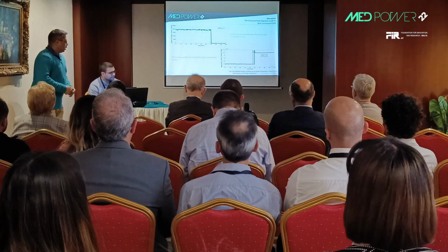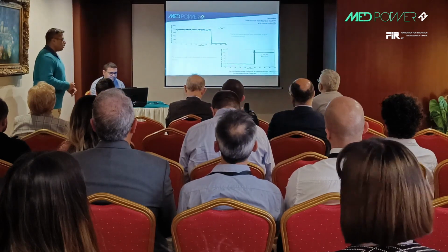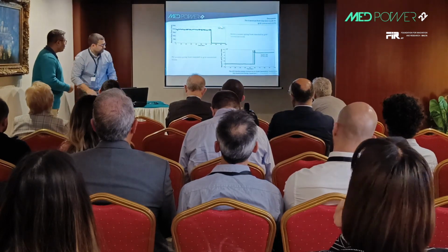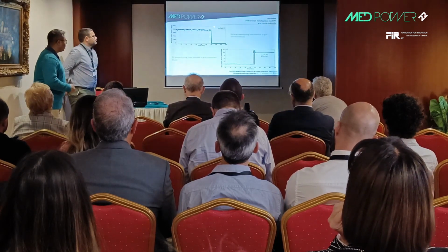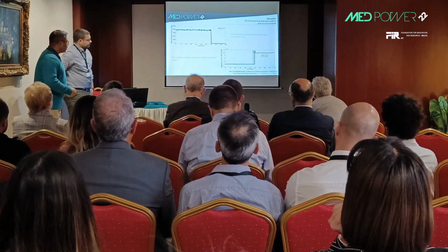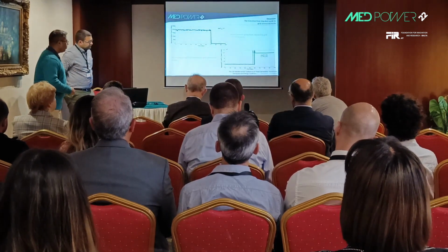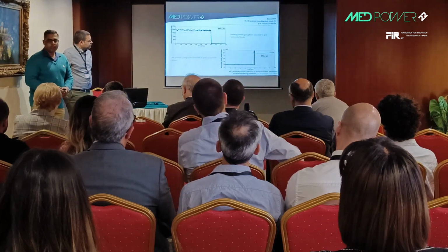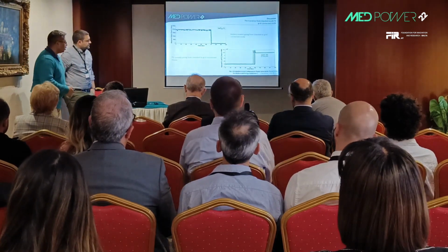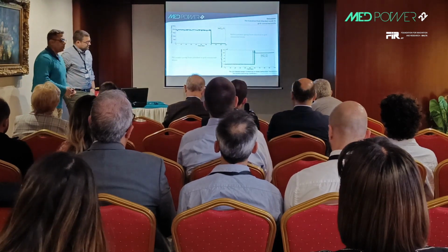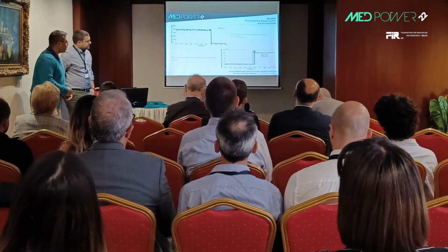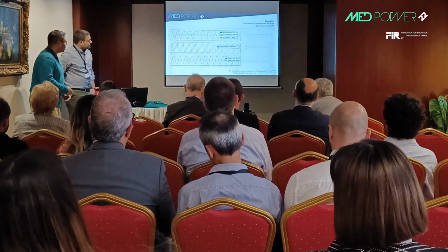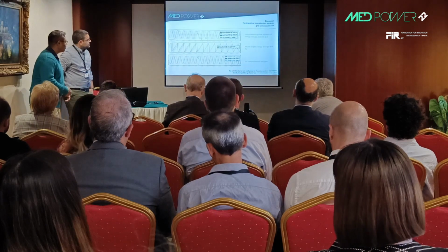And similarly, when we have the grid back, we can go from the islanded mode to the grid connected mode, and we have seen that we can go back to the grid connected mode without any kind of spurious transients, especially because of the synchronization strategy that we have developed. And these are some of the instantaneous voltage and current results that were obtained.